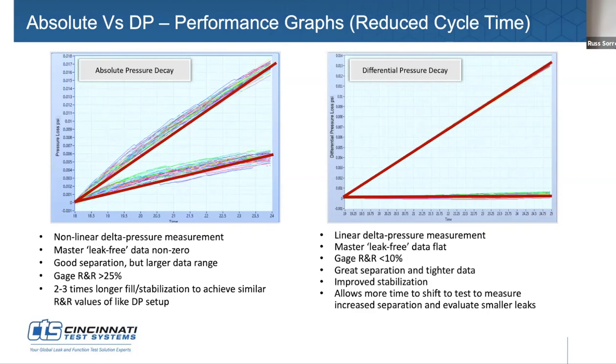We can only see it in, as you can see, these graphs right here on the absolute pressure decay graph, which show that thermal event. A great bit of it is due to the expansion and then eventual reduction in the air that's being put in there because of the pressure that we're having. So is that a correct assessment? Yeah, that's a really good description.